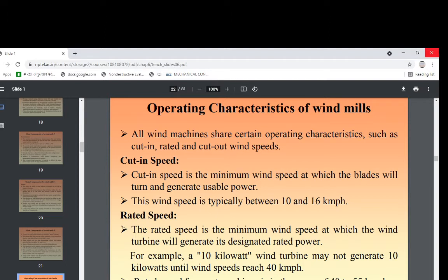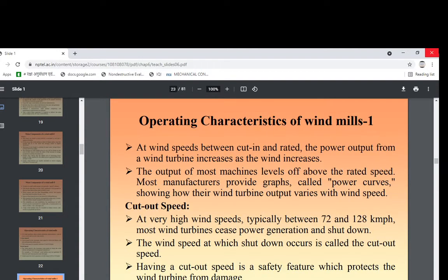Now rated speed. The rated speed is the minimum wind speed at which the wind turbine will generate its design rated power. For example, a 10 kilowatt wind turbine may not generate 10 kilowatt until wind speed reaches 40 km per hour. Rated speed for most machines is in the range of 40 to 55 km per hour.